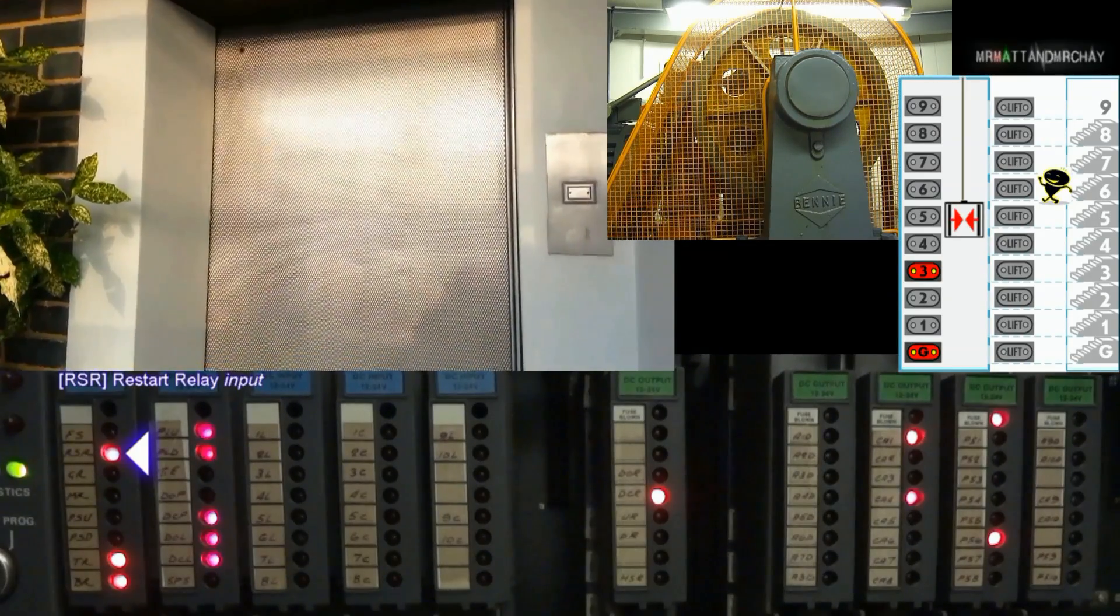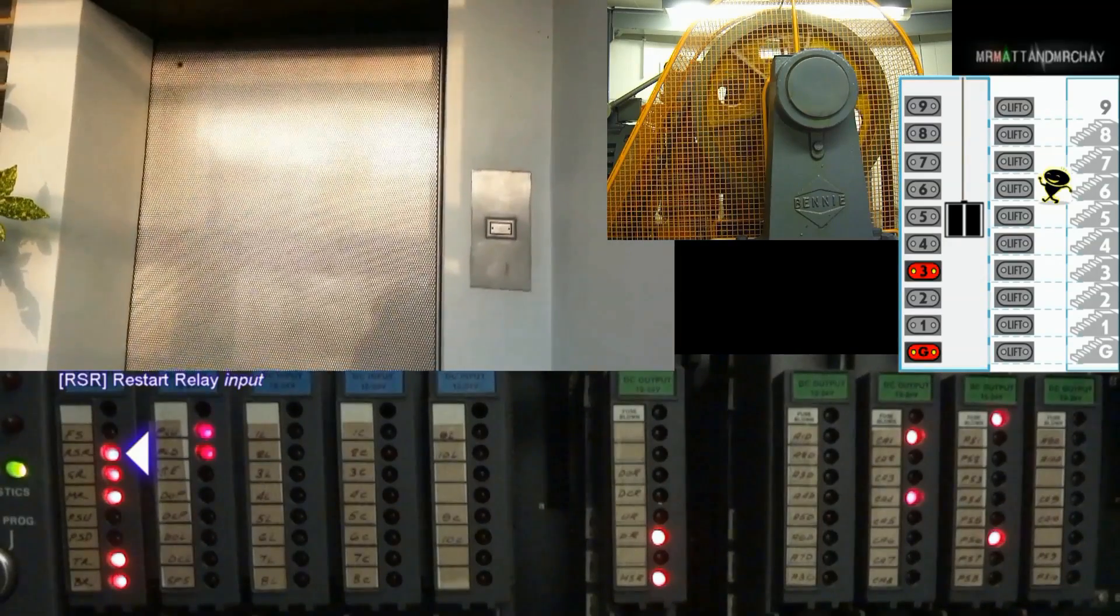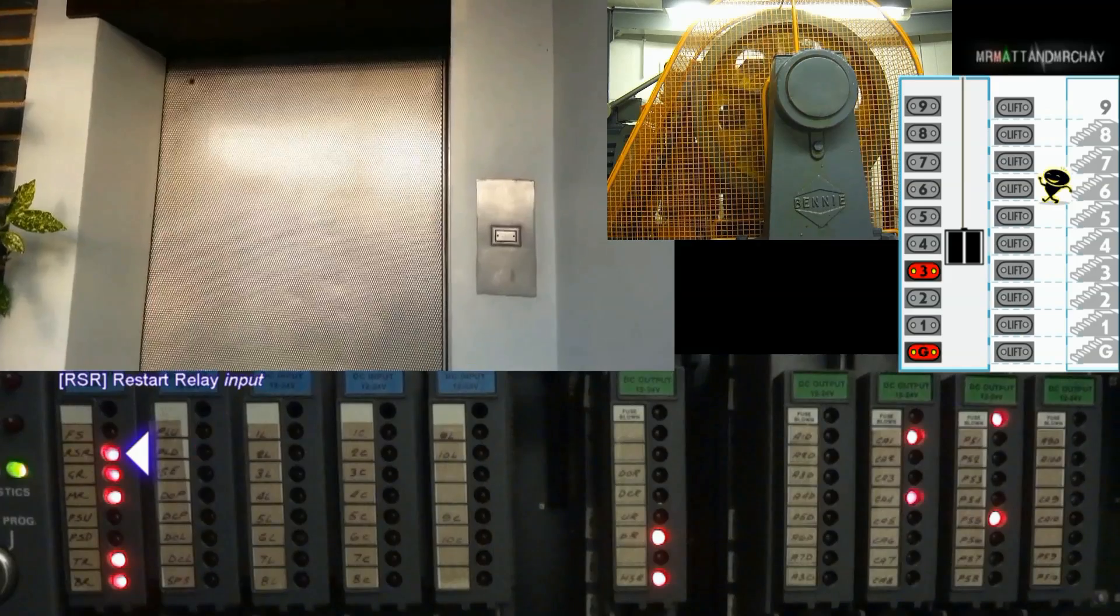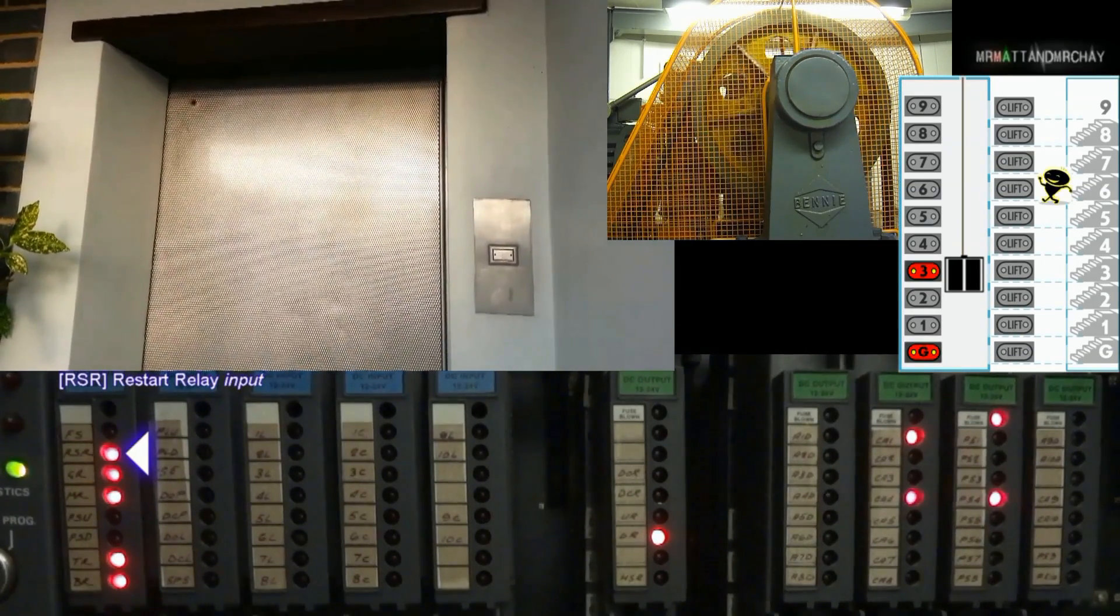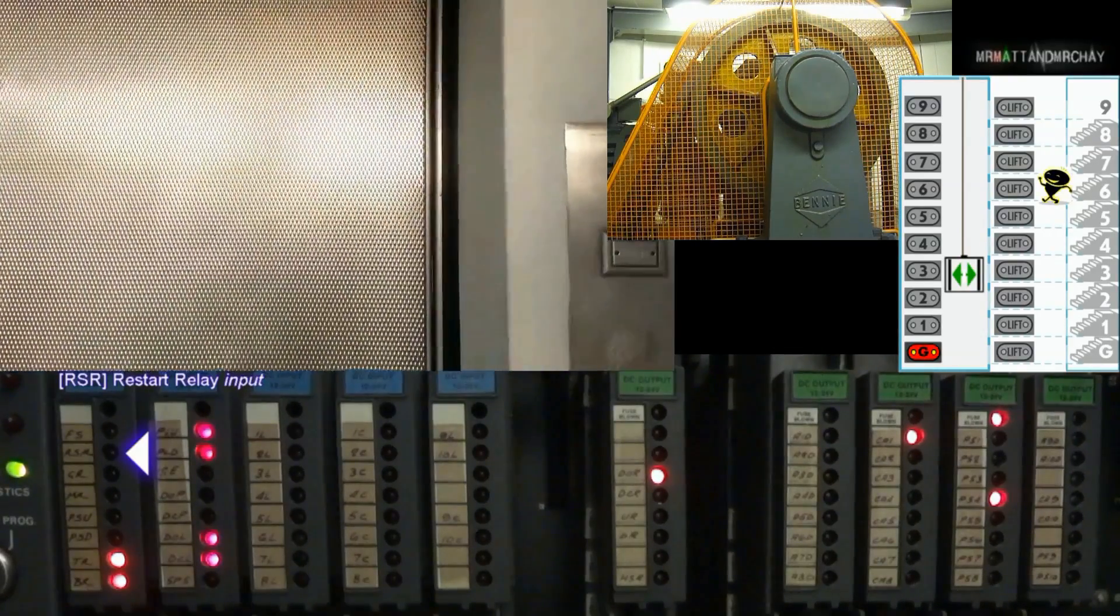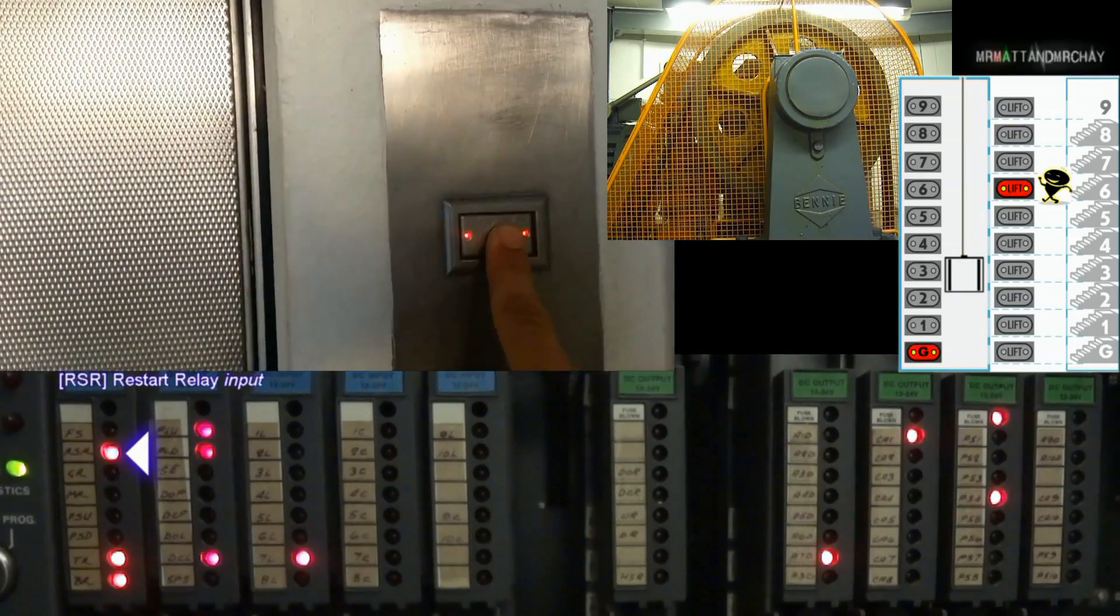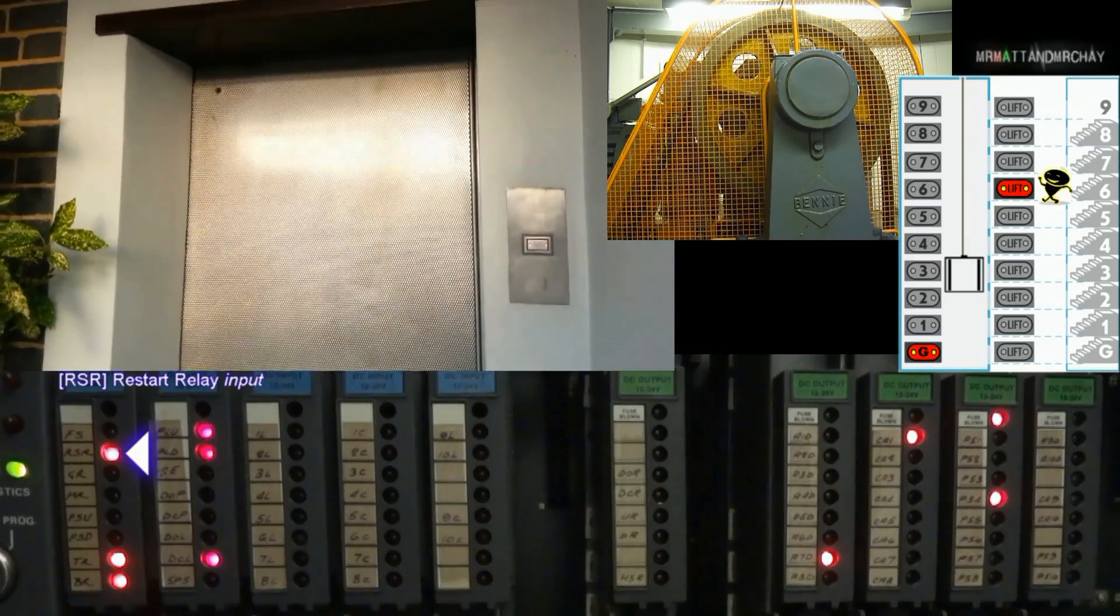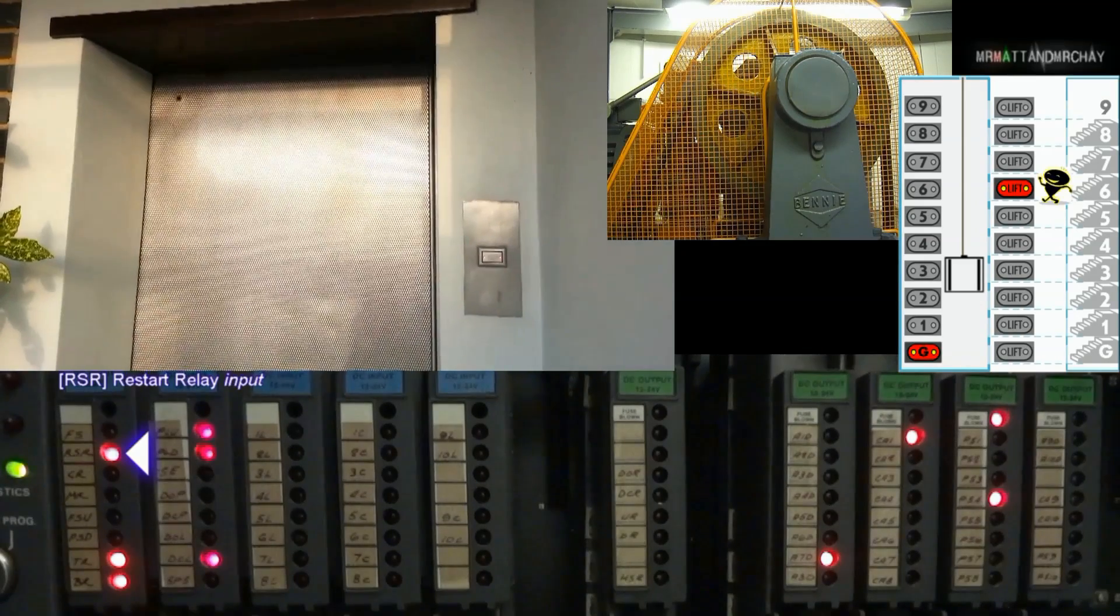RSR, restart relay. This is a timer relay at the top of the cabinet called PT, pause timer. This timer activates for a few seconds at the end of each run. This is probably to clear any relays or any other timers in readiness to run again. I'm not 100% sure of the purpose of this input, although it probably informs the controller that the reset sequence has completed, so the controller will allow the lift to run again.